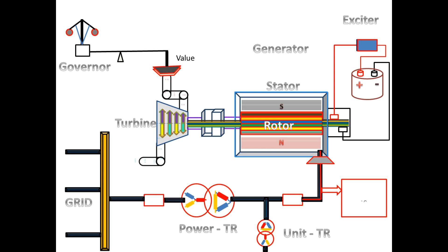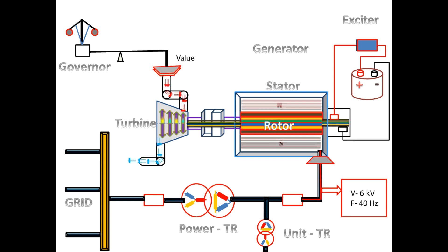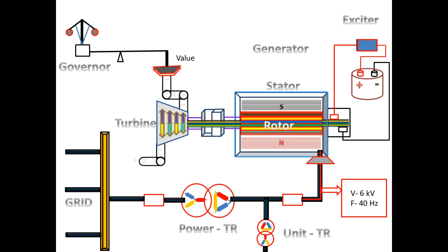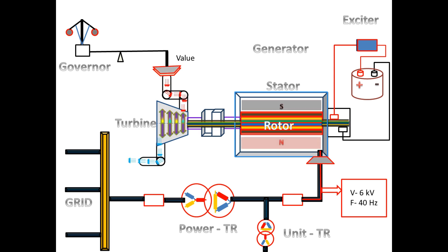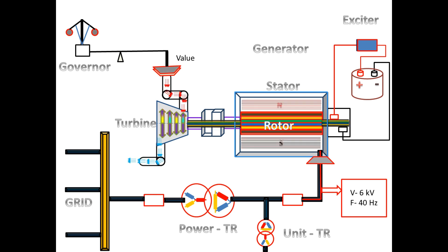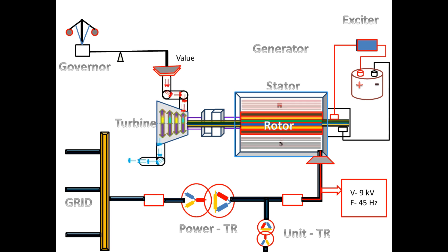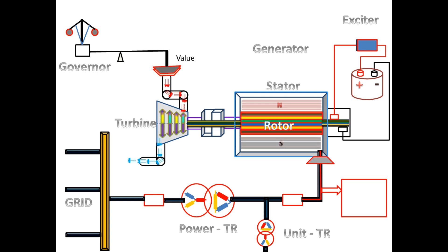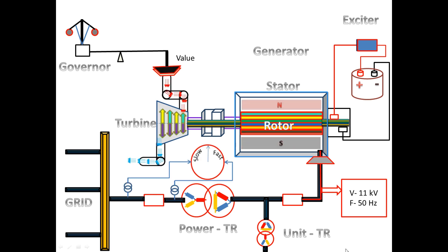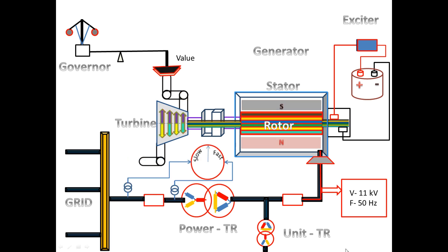When the speed starts to increase gradually, the voltage will also start to build up. When the generator reaches the rated speed, it will produce the rated voltage and frequency. When it reaches the rated voltage and frequency, then only we have to close the generator breaker.